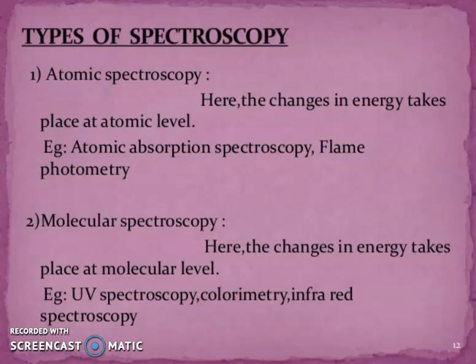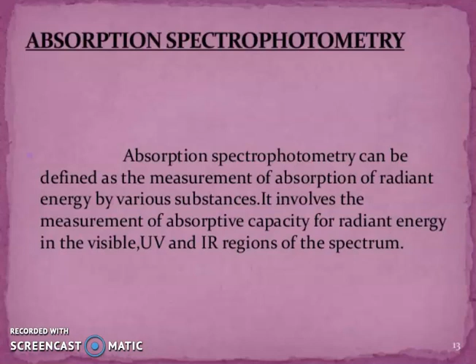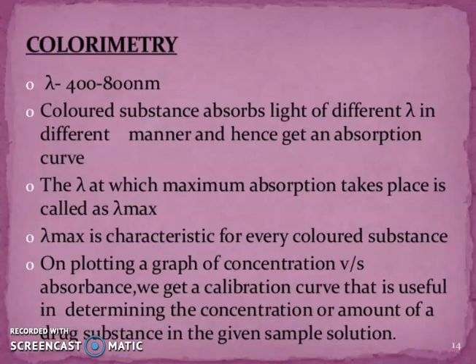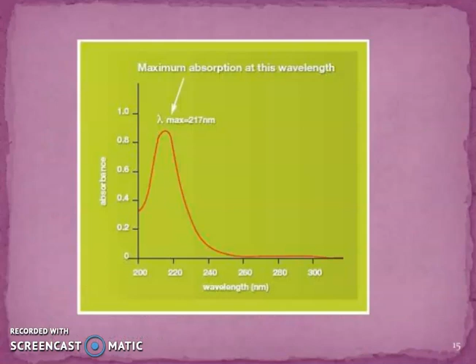Absorption spectrophotometry can be defined as the measurement of the absorption of energy by various substances. It involves the measurement of absorptive capacity for radiant energy in the visible, UV and IR regions of the spectrum. So, colorimetry. Colored substances absorb light of different wavelengths in different manners and hence give an absorption curve. The wavelength at which maximum absorption takes place is called lambda max. Lambda max is characteristic for every colored substance. On plotting a graph of concentration versus absorbance, we get a calibration curve that is useful in determining the concentration or amount of a drug substance in the given sample solution. You can see the maximum absorption at this wavelength.